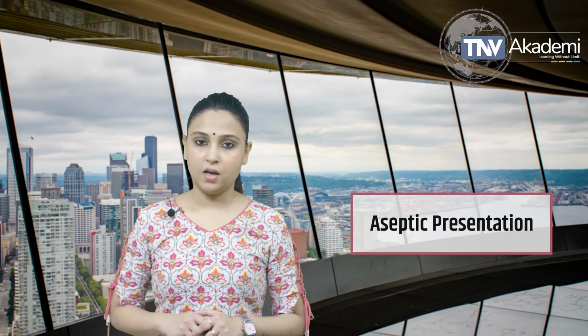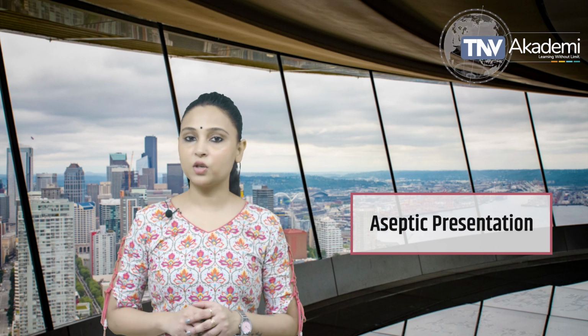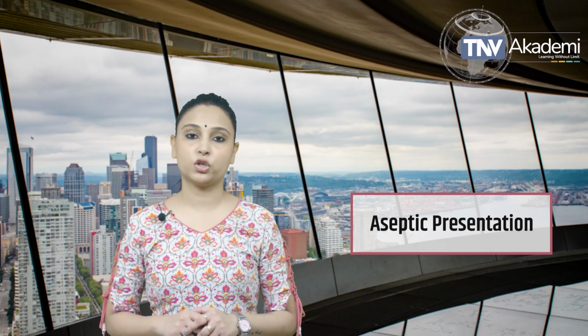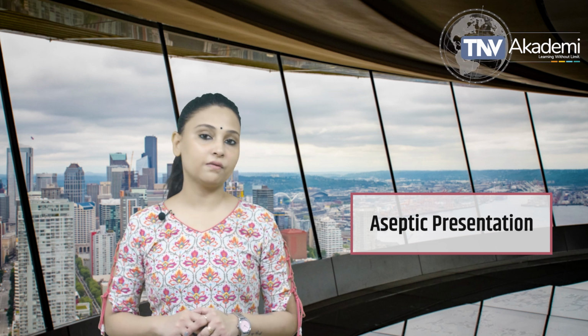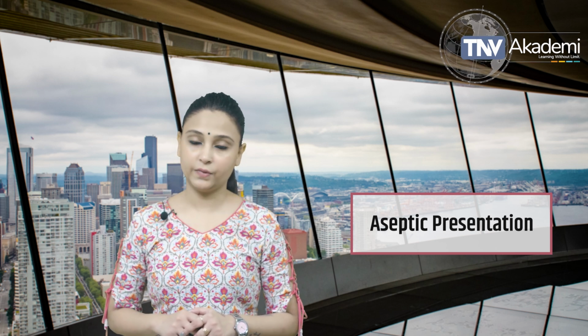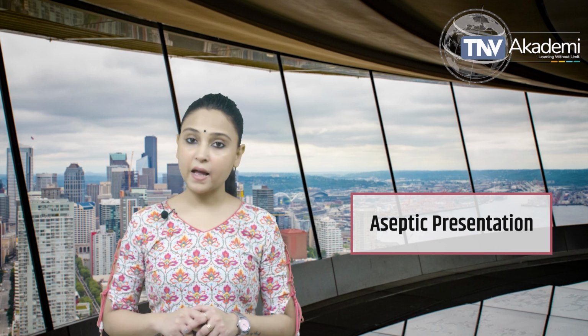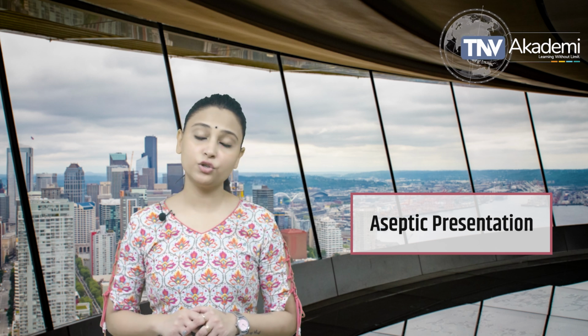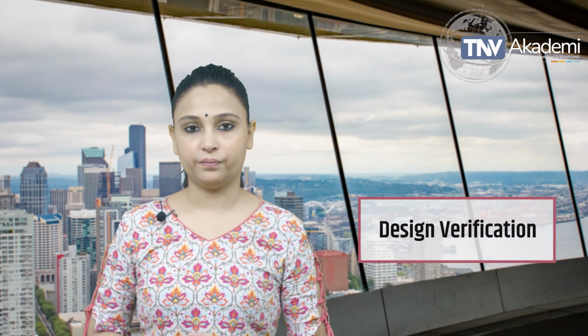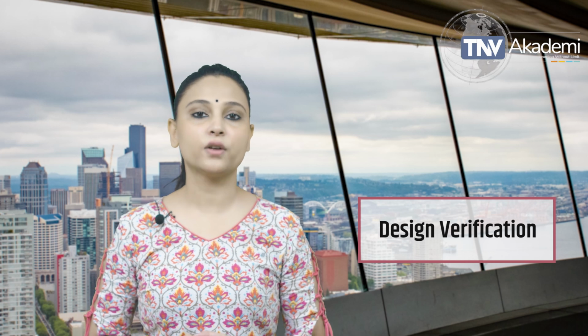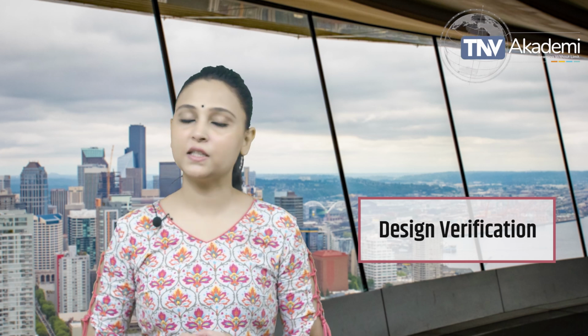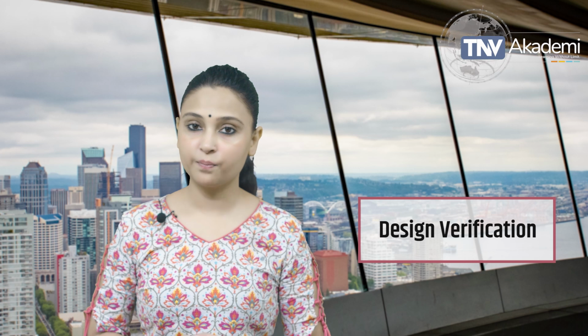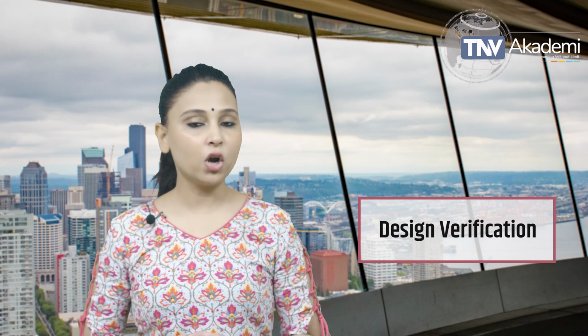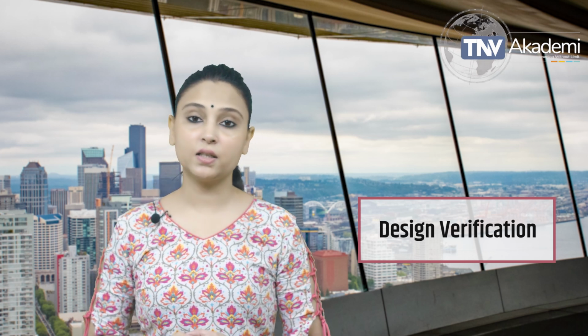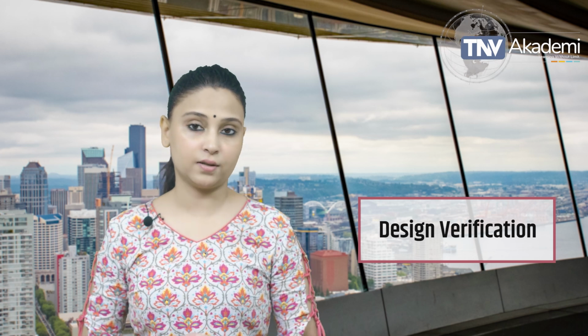Aseptic presentation. The design should facilitate aseptic presentation, meaning that healthcare professionals can access and use the medical device without contaminating it. This includes clear instructions and designs that minimize the risk of contamination during opening. Testing and validation. Design verification. Design verification involves testing to ensure that the packaging design meets the specified requirements. This includes integrity testing, ensuring that the packaging remains intact and maintains sterility under various conditions.